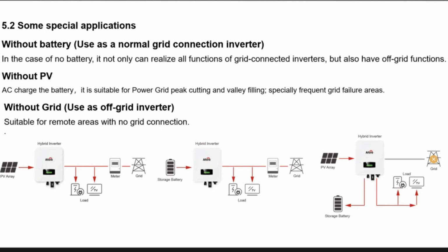So except for the previous applications, the string inverter also has some other special uses. For example, the hybrid inverter can operate without a battery. Some users want the hybrid inverter but install the battery later. It can work. Under this condition, the hybrid inverter works as a normal grid-connected inverter. Later, when the battery is on, they can do some peak shaving or off-grid backup.